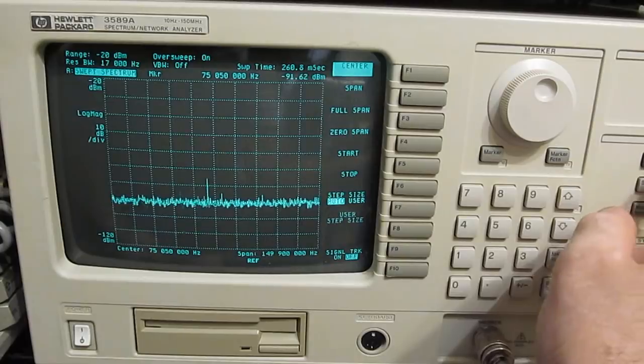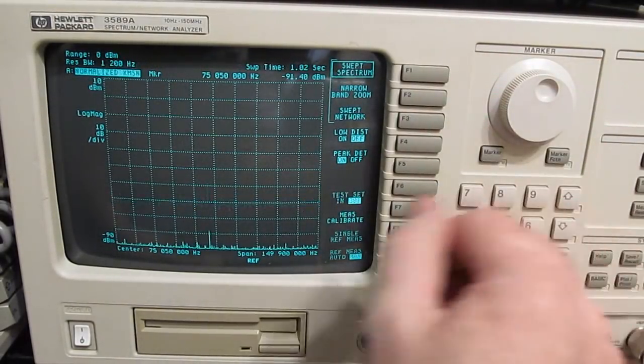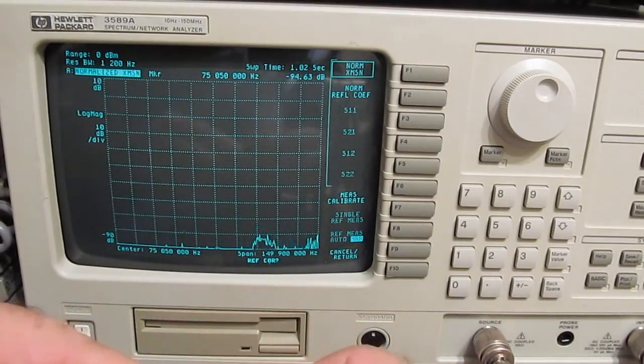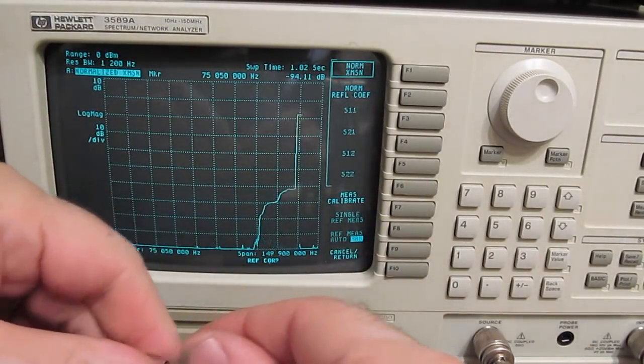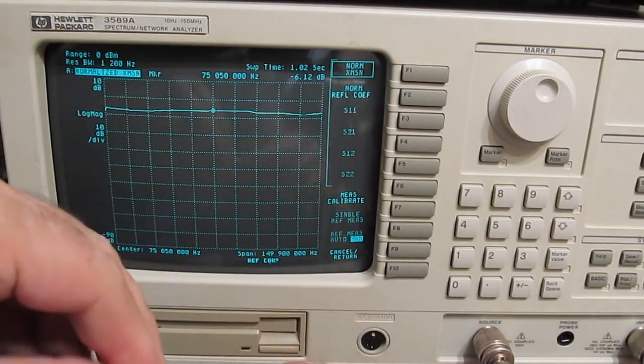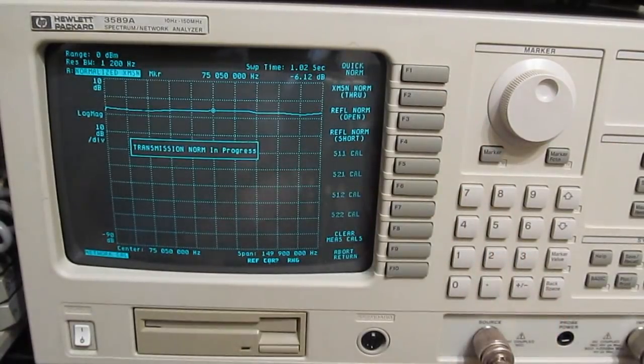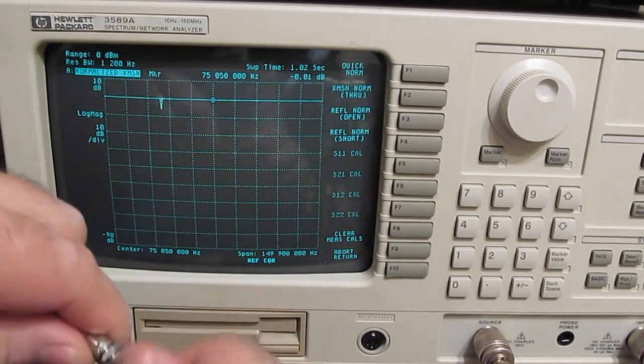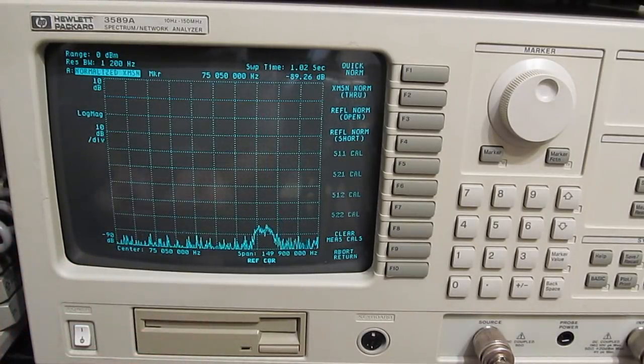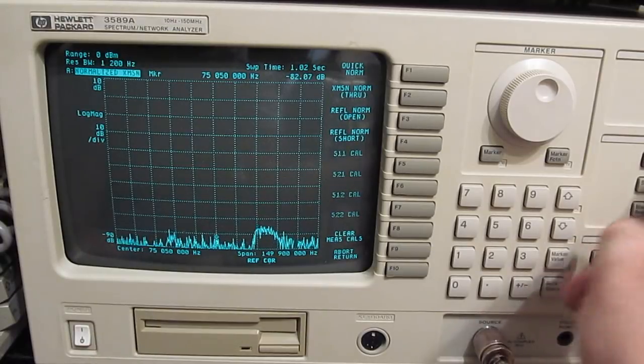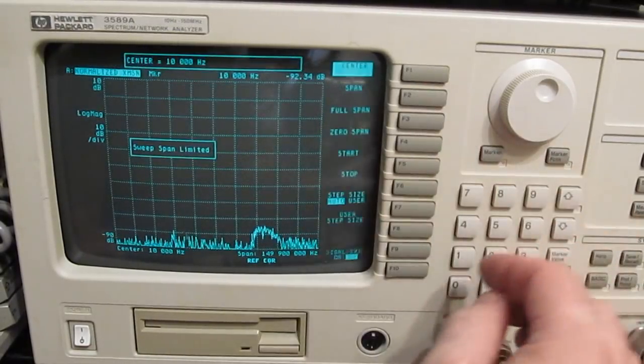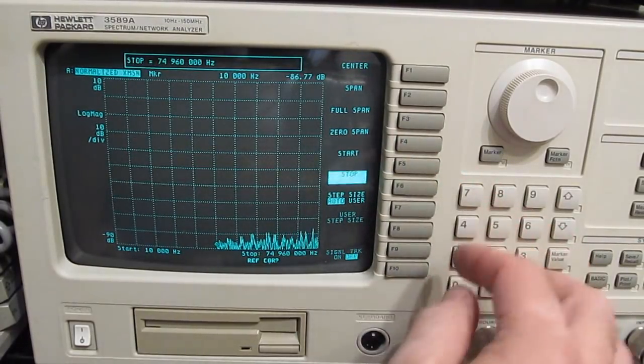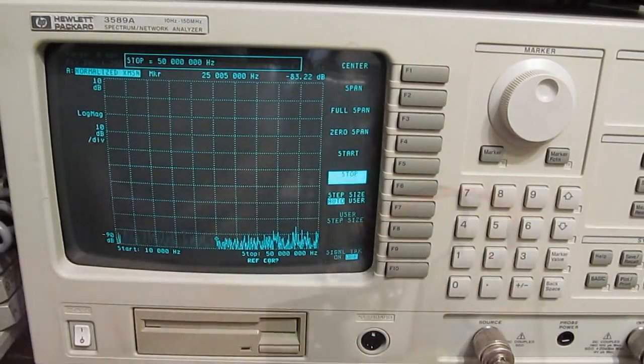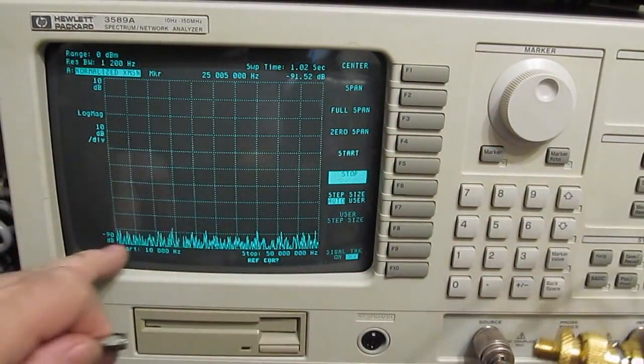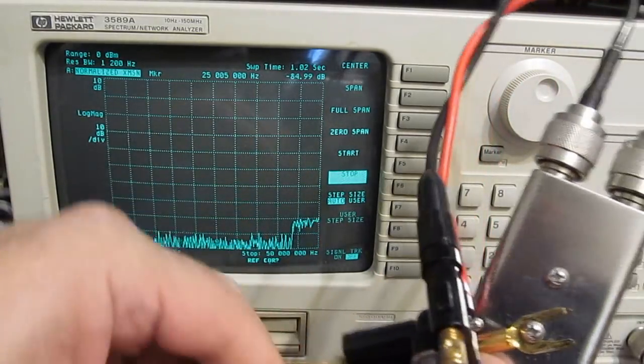So let's just see. We'll go to measurement type, network analyzer, and we'll short the two inputs together. And we can do measure cal and measurement through. Let's do a start frequency, just give it 10 kilohertz, and let's say a stop frequency of 50 megahertz. So with the leads disconnected, of course we're reading, this is minus 90 dB down. Probe's not going to be that good, I'll guarantee you that.